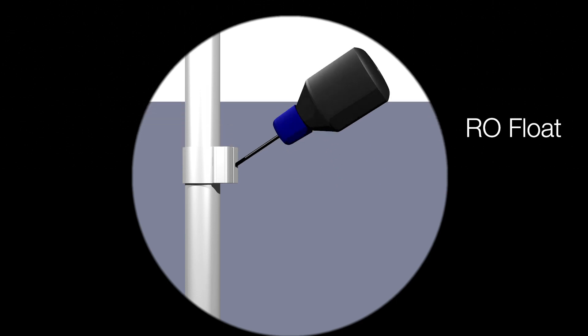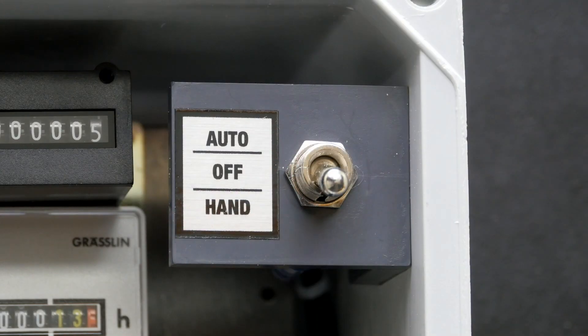If no redundant off float is present, the pump will continue to run until the tank is empty. Please note that if the control panel is equipped with a redundant off, or RO float, the panel must verify that the float is in the up position before the pump will engage, even in the manual mode.